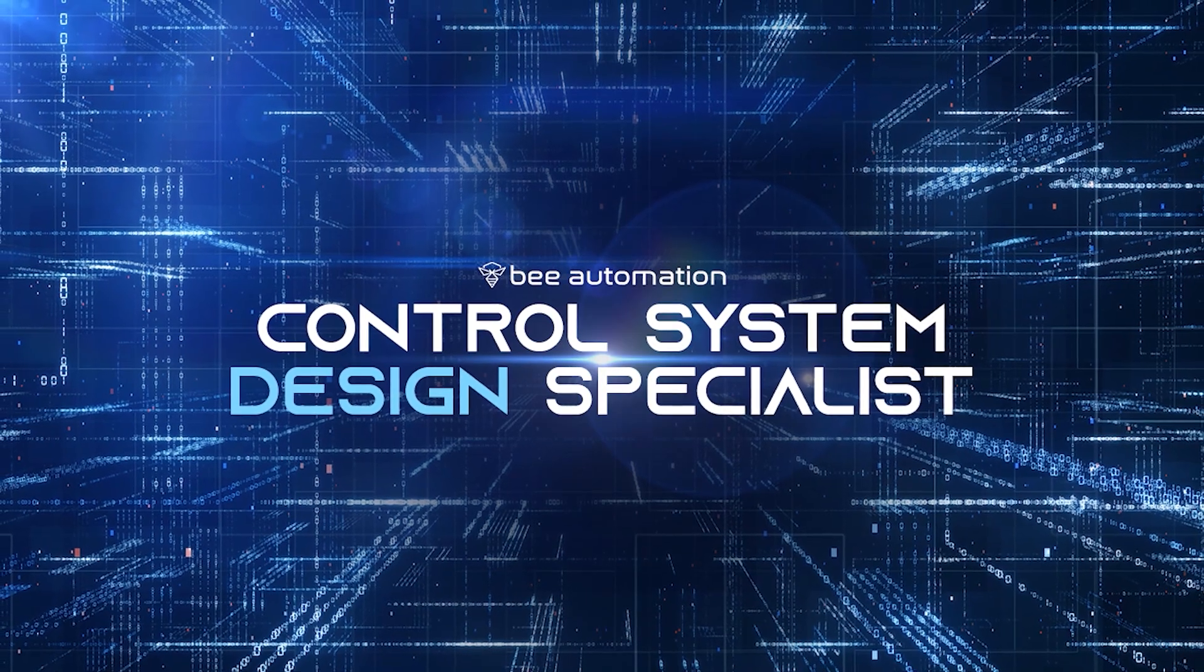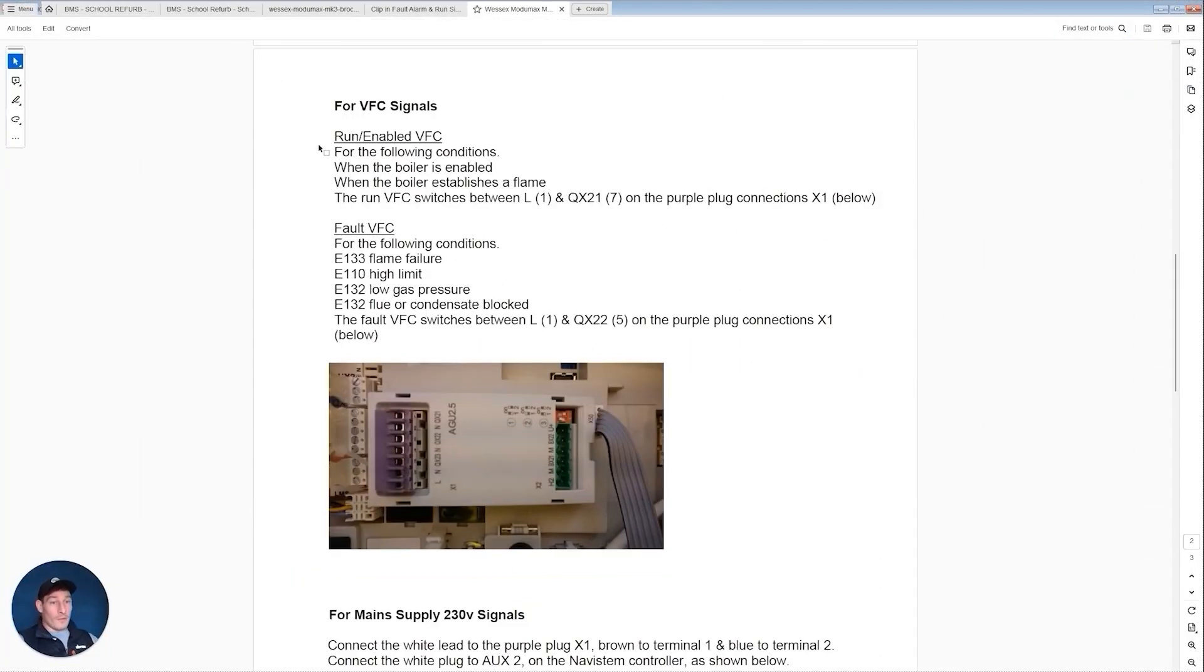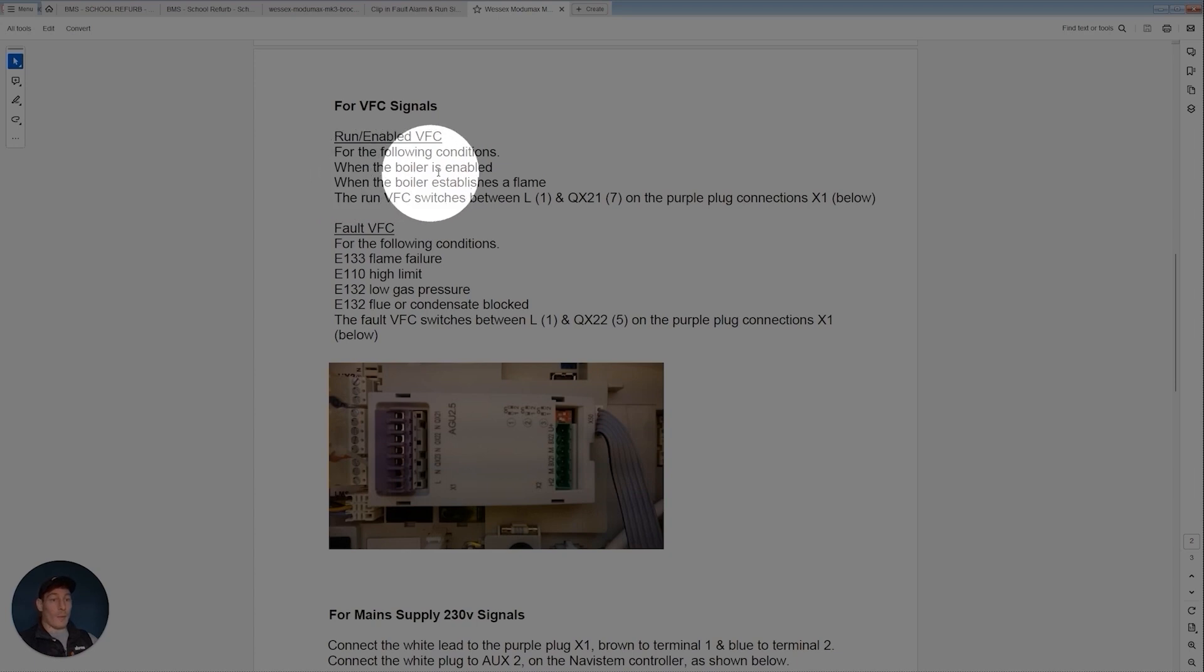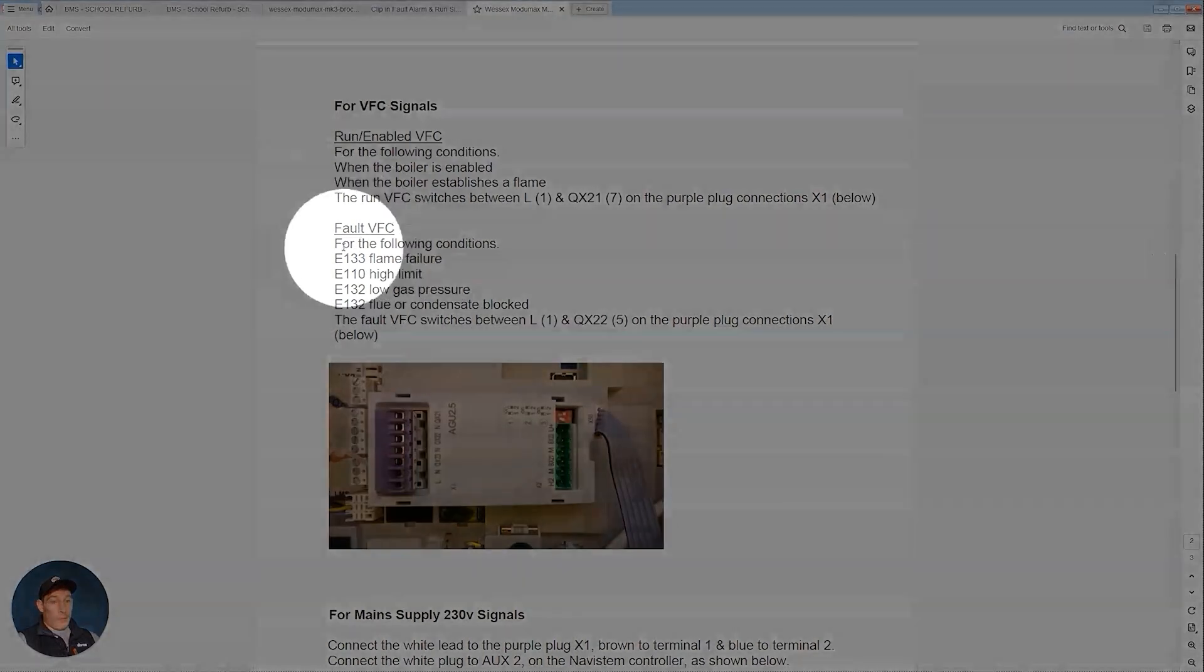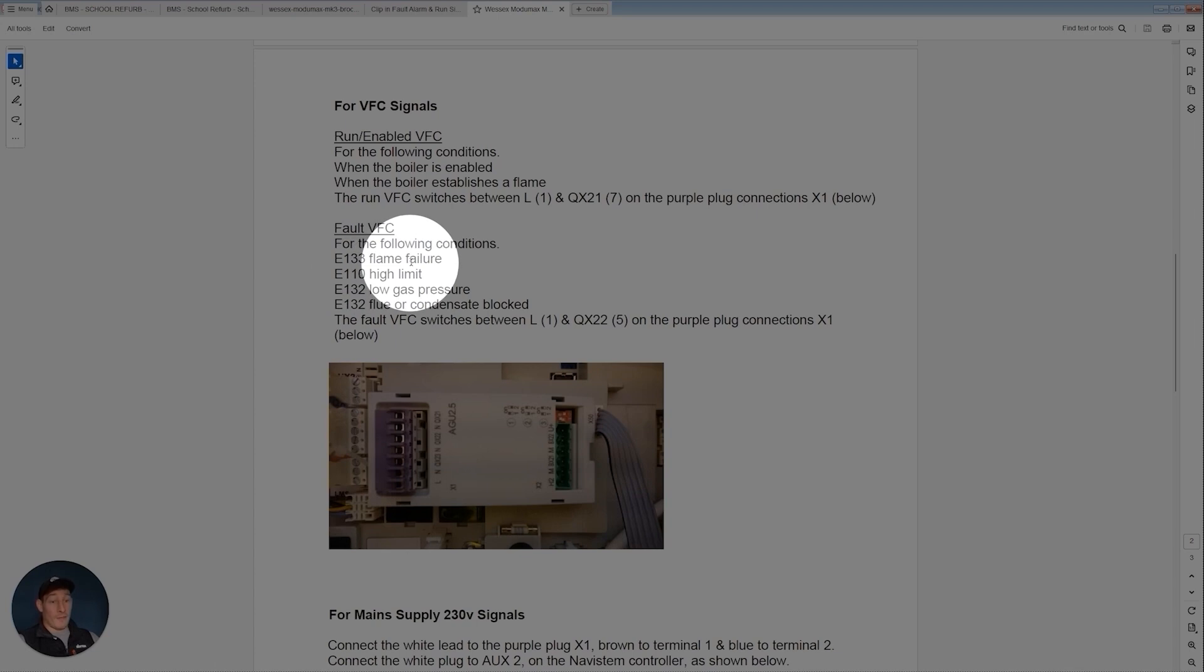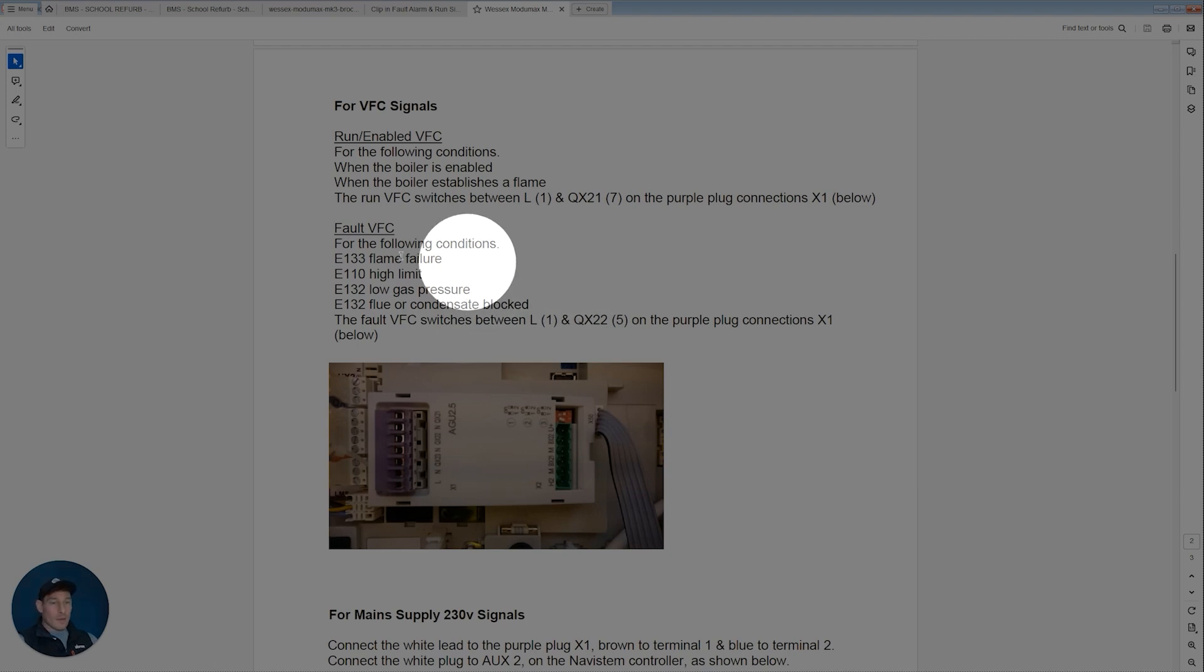Just a quick overview of the run/enable signal. This comes on when the boiler is enabled, when the boiler establishes a flame. And then for the fault signal to be triggered, the following conditions need to apply: there's a flame failure, there's a high limit whatever that correlates to that code which can be found somewhere, low gas pressure, and/or flue or condensate blocked. So that's what brings on the fault output on the boiler.